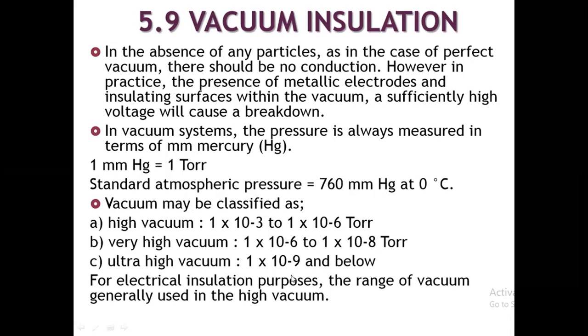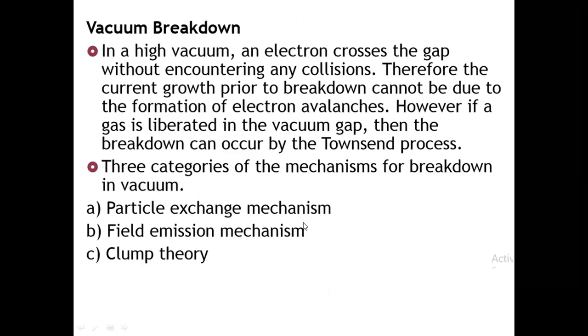For electrical insulation purposes, the range of vacuum generally used is high vacuum. Vacuum can be used as a dielectric. In a high vacuum, an electron crosses the gap without encountering any collision, therefore current growth prior to breakdown cannot be due to electron avalanche formation. However, if gas is liberated in the vacuum gap, breakdown can occur by the Townsend process.